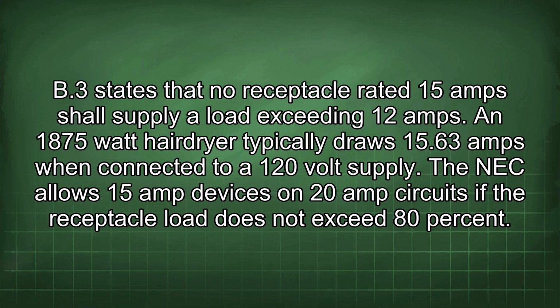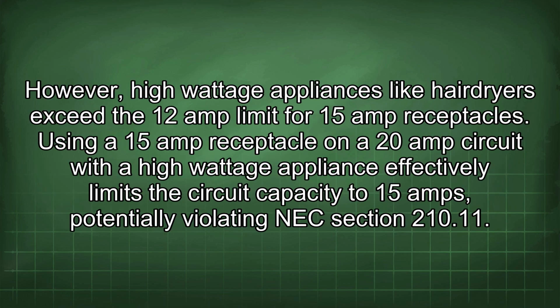The NEC allows 15-amp devices on 20-amp circuits if the receptacle load does not exceed 80%. However, high-wattage appliances like hairdryers exceed the 12-amp limit for 15-amp receptacles. Using a 15-amp receptacle on a 20-amp circuit with a high-wattage appliance effectively limits the circuit capacity to 15 amps, potentially violating NEC Section 210.11.